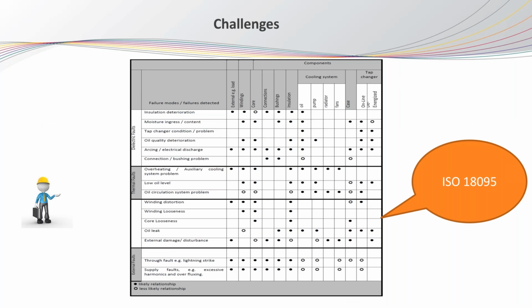And the other challenge that faces the electric utilities is the cause of the failure of the power transformers. Power transformers cannot be considered as a single element or a component in the network when it comes to the failure analysis. Just as an example to that, I brought here a slide from the ISO 18095, and you can see here, I will bring my laser pointer, that the transformer is divided into a number of components. You have the winding, you have the core, connection, bushing, cooling system, and tap changer. And for each of these components, it has its own failure mode. You have the dielectric faults or the dielectric failure mode, and they are divided into a number of failure causes. You have the same for the thermal fault and the mechanical faults and the external faults.